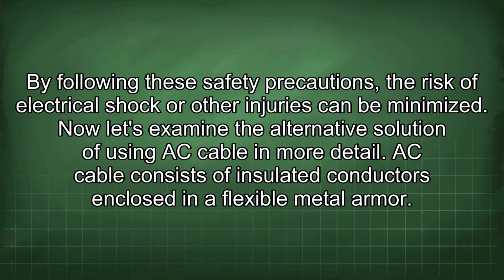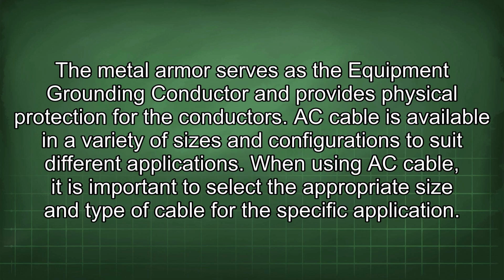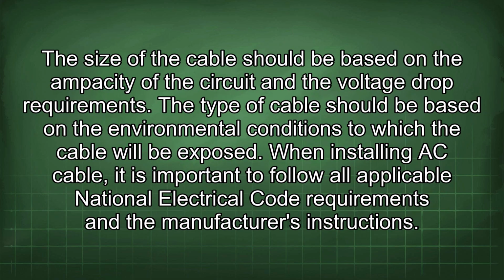AC cable consists of insulated conductors enclosed in a flexible metal armor. The metal armor serves as the equipment grounding conductor and provides physical protection for the conductors. AC cable is available in a variety of sizes and configurations to suit different applications. When using AC cable, it is important to select the appropriate size and type of cable for the specific application. The size of the cable should be based on the ampacity of the circuit and the voltage drop requirement. The type of cable should be based on the environmental conditions to which the cable will be exposed.